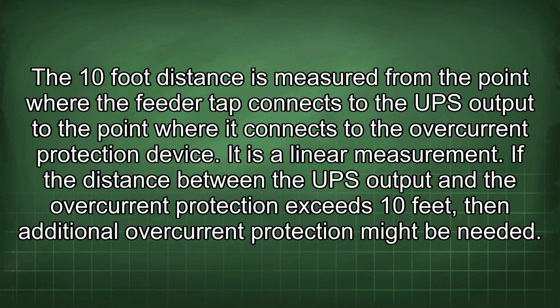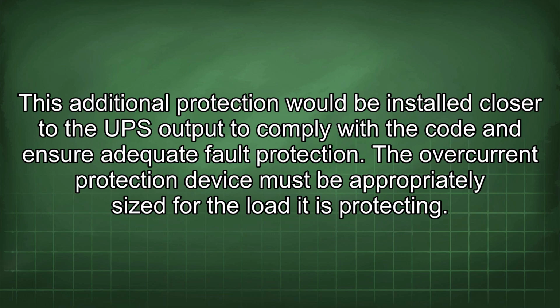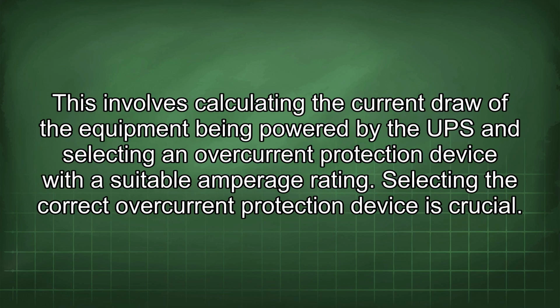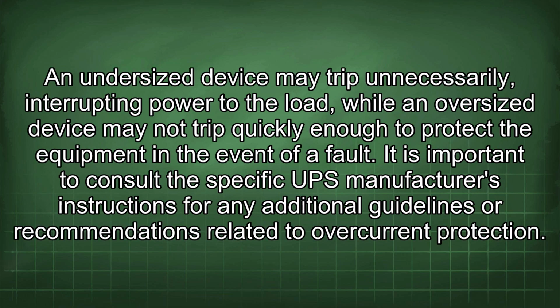If the distance between the UPS output and the overcurrent protection exceeds 10 feet, then additional overcurrent protection might be needed. This additional protection would be installed closer to the UPS output to comply with the code and ensure adequate fault protection. The overcurrent protection device must be appropriately sized for the load it is protecting. This involves calculating the current draw of the equipment being powered by the UPS and selecting an overcurrent protection device with a suitable amperage rating. Selecting the correct overcurrent protection device is crucial. An undersized device may trip unnecessarily, interrupting power to the load, while an oversized device may not trip quickly enough to protect the equipment in the event of a fault.